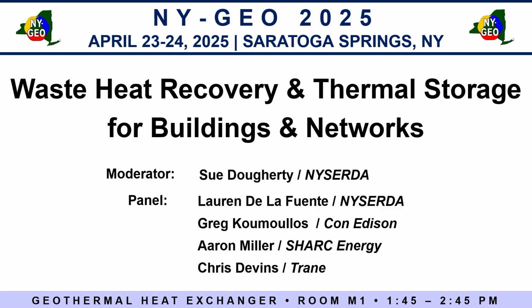Right now we have this one main steam service that feeds all 11 buildings of that facility, so the main steam service going into the building we're keeping. But on top of that, we're also having a new dedicated small service just for Con Ed, with a shell tube heat exchanger that's our backup heat for the whole system. So if, for whatever reason—since we're a utility, it's probably not needed, and if you're doing it on the private side you probably wouldn't have this level of redundancy—but we want to ensure we can inject heat into our loop to make sure they have heating there. So it's staying in place, and the radiators are going to stay in place too, just so we don't have to disturb them in the residents' apartments.